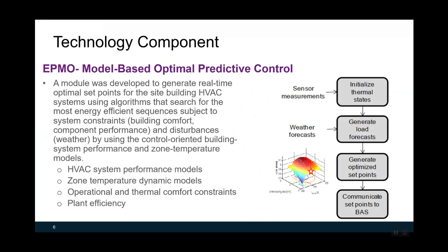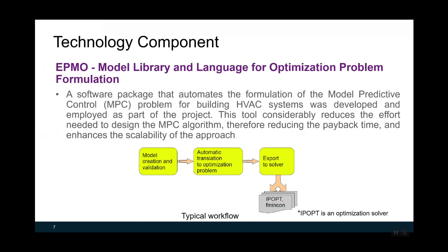The figure on these slides shows the key steps for model predictive control. The next key component is the model library and the language for optimization problem formulation. A software package that automates the formulation of MPC problems for building and HVAC systems was developed as part of this project. This significantly reduced effort needed to design MPC algorithms, thereby reducing the payback time and enhancing the scalability of the proposed approach. The figure shows the typical workflow, including model creation, validation, automatic translation to optimization problem, and export to a solver.